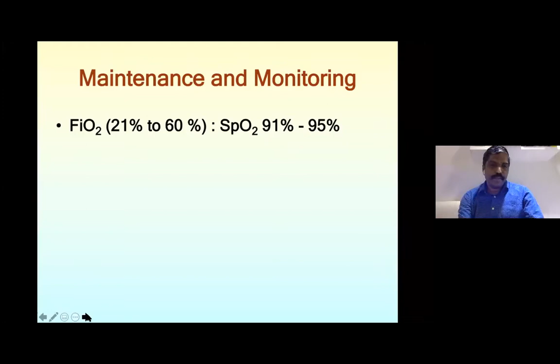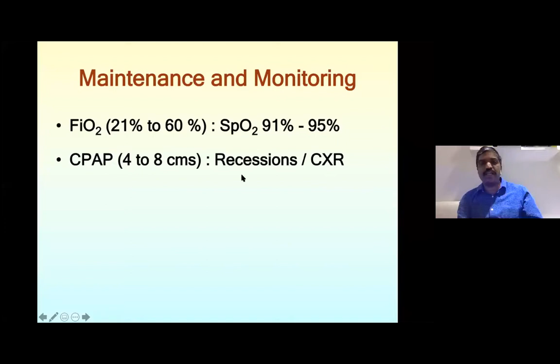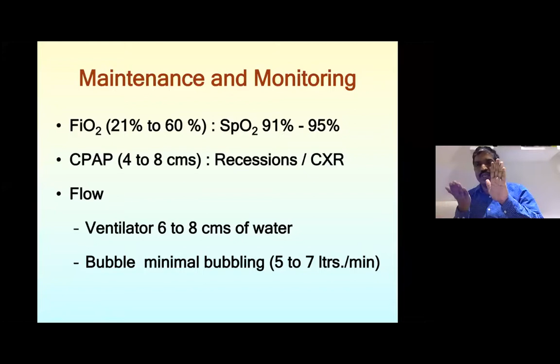CPAP pressure should be between 4 to 7. Some people use up to 8. So increasing pressure is based only on retractions or X-ray. As I already told you, if retractions are there, you will increase the pressure. If X-ray is showing low volume, increase the pressure. Flow, in ventilator, it can be 6 to 8 liters. I've already said flow is 5 liters fixed, but if no bubbling in the bubble chamber, increase to 6. Still no bubbles, increase to 7. No bubbles, there is definitely a leak in the circuit.